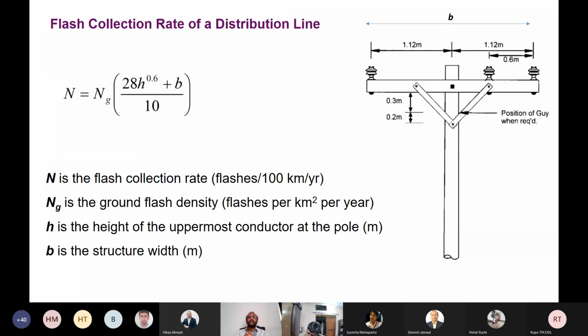Now I'm going to the protection of distribution lines. Before coming to the substation, we have to make sure that, as I told you, the MV lines are much more exposed to lightning than LV lines, which are mostly in built-up areas. You have to be very careful about how to manage the lightning coming into the MV lines, which are leading to the transformer.